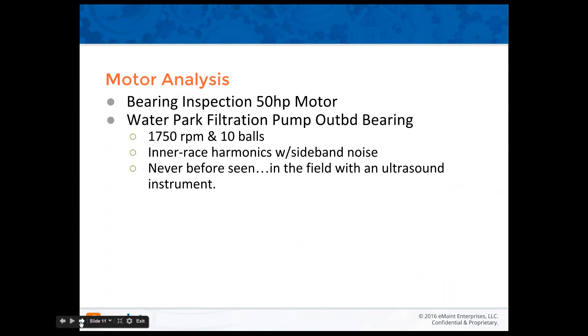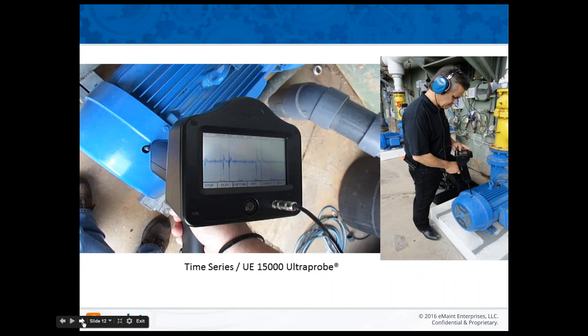For the motor analysis or bearing inspection case study: I was looking at a 50 horsepower motor at a water park in the Atlanta area — a filtration pump outboard bearing, 1,750 RPMs, 10 balls. The inner race showed harmonics with sideband noise — never before seen in the field with an ultrasound instrument up to that point. Looking at the back of the Ultraprobe 15,000, you see the time waveform clearly showing faults and indications. The FFT screen showed faults coming up at 1,750 RPM, and the sideband noise was clearly indicative of an inner race problem.